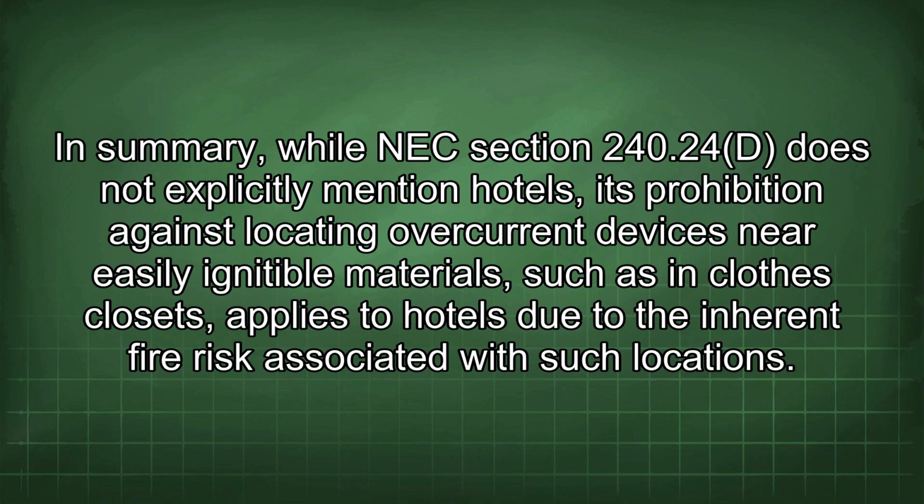In summary, while NEC Section 240.24(D) does not explicitly mention hotels, its prohibition against locating overcurrent devices near easily ignitable materials, such as clothes closets, applies to hotels due to the inherent fire risk associated with such locations.